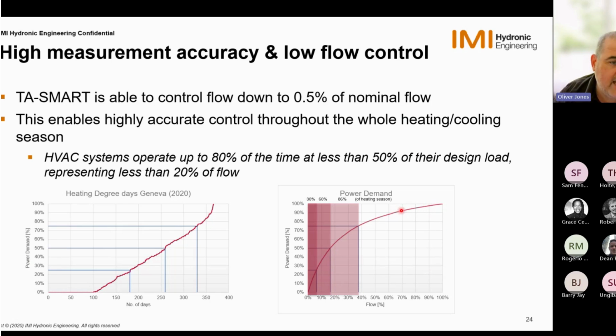So where we're getting up to the high 80% and 90%, typically we're only talking days here throughout the year itself. So it's a very small amount. Whereas, as we say, at 50% load, we're covering 80% of that heating season. So as you can see, this is a very steep curve.